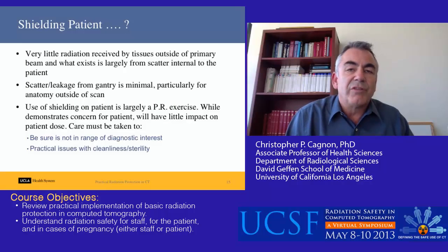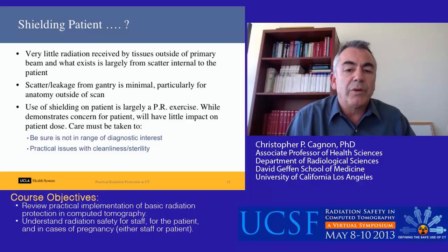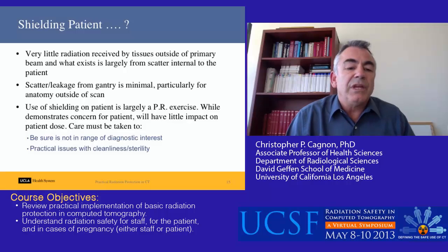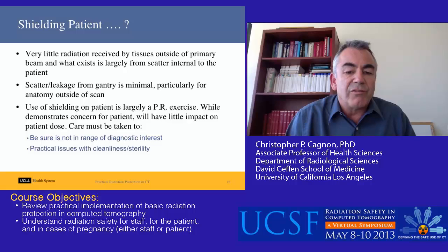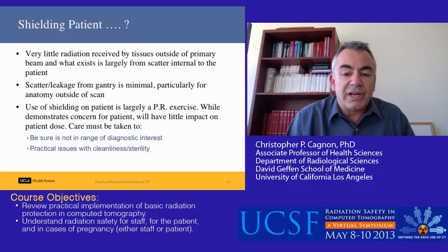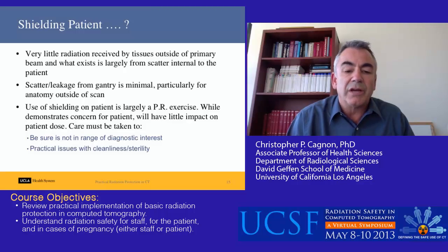What does this mean for shielding the patient? Very little radiation is received by tissues outside the primary beam, and what exists is largely scatter internal to the patient. Scatter and leakage from the gantry is minimal, particularly for anatomy outside the actual scan length. This means the use of shielding on a patient is largely a public relations exercise — while it demonstrates concern for the patient, it will have almost no impact on actual patient dose. If you do use shielding, ensure it is not in the range of diagnostic interest, as it will cause tremendous artifacts, and there are practical concerns regarding cleanliness and sterility.